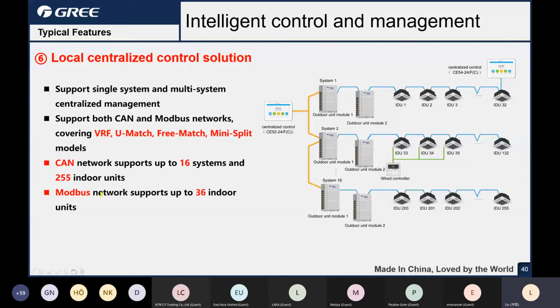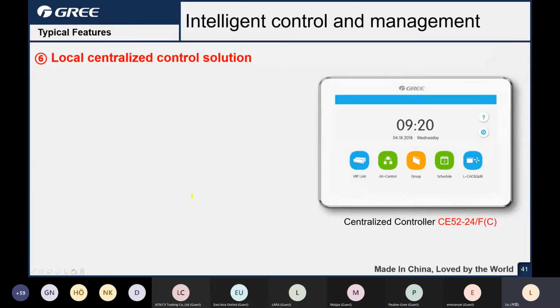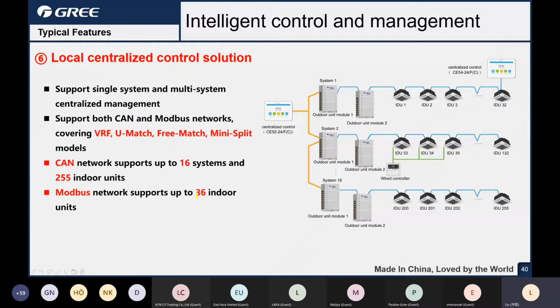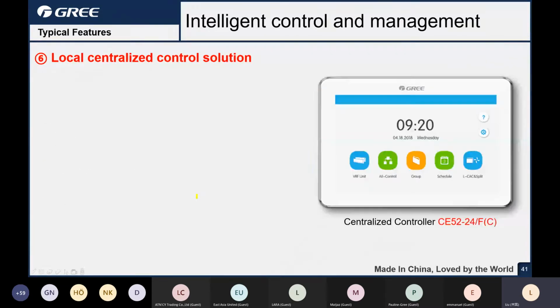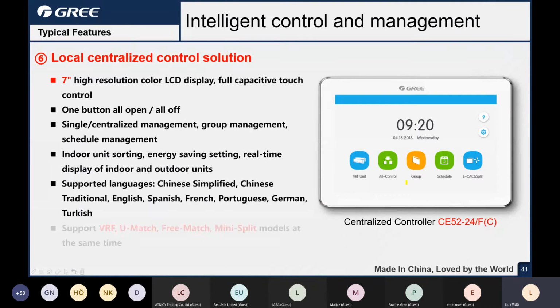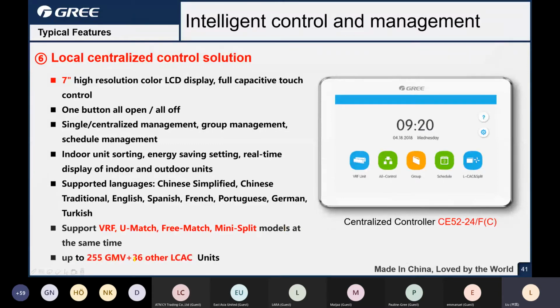And for the Modbus network, there are a lot of ports on the central controller. One central controller can support 36 indoor units. Okay, that's the maximum quantity of units it can support. Okay, for this CE52, the big size central controller, it is 7-inch. And this central controller can support all of the VRF and LCAC, light commercial, and VRF, and RAC, mini split can be supported by the CE52. And that's the total amount, CAN network and Modbus network, that's the total.